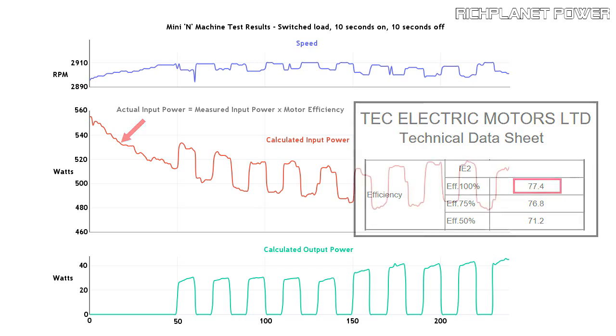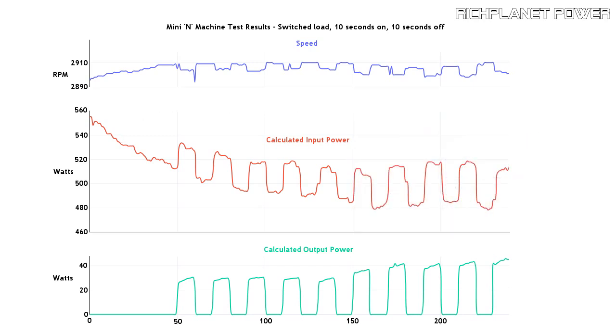Looking at the graph, the top blue line is the generator speed, which you can see decreases slightly each time the load is switched on, and then increases again when it's switched off. This means that there is some back torque felt on the shaft as a result of the electrical power generation. This is because of the way an induction motor works.